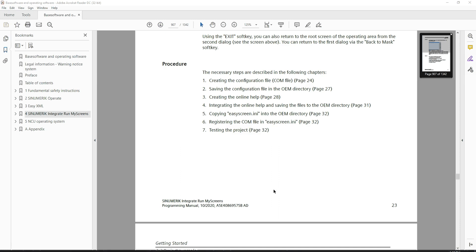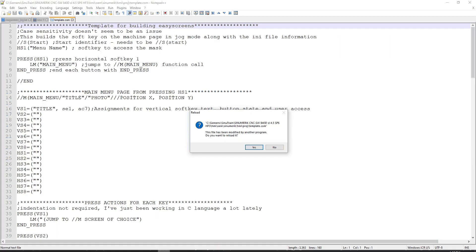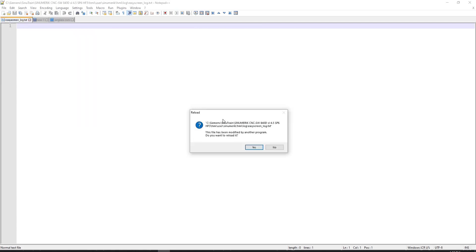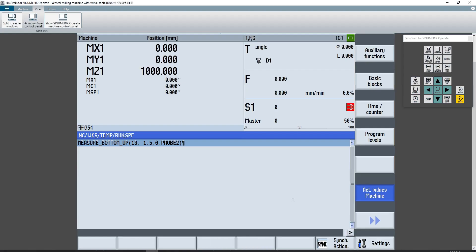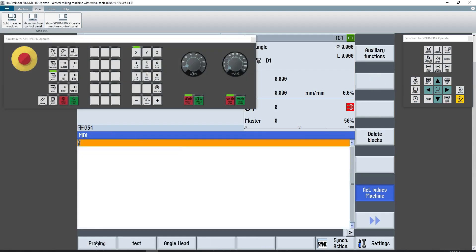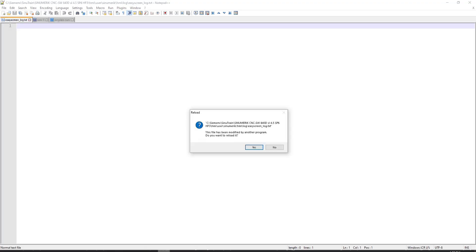I found that a good software to use for debugging the Siemens easy screens is Notepad++. The reason for that is that whenever you load up a new screen, you'll get a little warning, as you may have just seen. If I load this screen up, I go to Notepad++, and you're going to see that it's going to say this file has been modified by another program. Do you want to reload it? And when you say yes, all of the errors that are created are then loaded up into Notepad++.